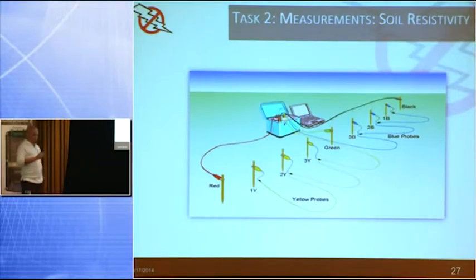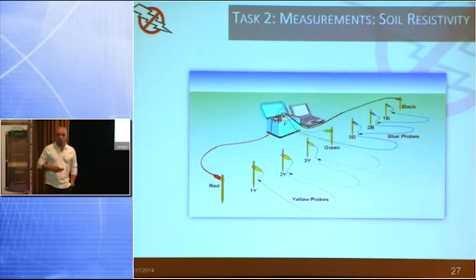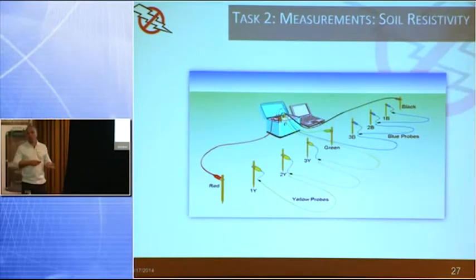So resistivity. All right, you saw Nate talking about it earlier, and we will put in multiple ground rods. Key difference here is your typical soil resistivity test, your typical meter has a 1-foot ground rod. It doesn't really inject a signal very deep. We have a 1 meter ground rod. This will inject over 350 foot deep.